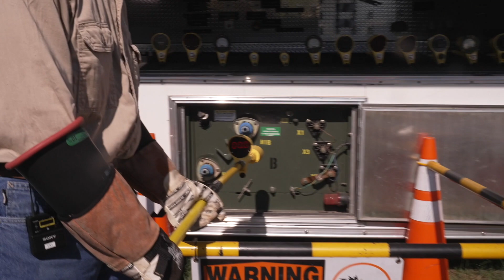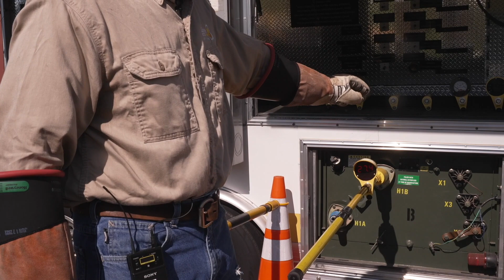Let's put it in OH, overhead. If you use any of our tools in the wrong position, the tool gives you an inaccurate reading - it doesn't hurt the tool. So for instance, overhead, now we're reading 27,000 volts, but we know it's actually 19.9, closer to 20,000 volts. So that's inaccurate - the tool is telling us either it needs calibration, since we're using it on a live known voltage source, or it's in the wrong position. Let's put it back in URD, underground residential distribution, and make contact. There we go, accurate, okay?